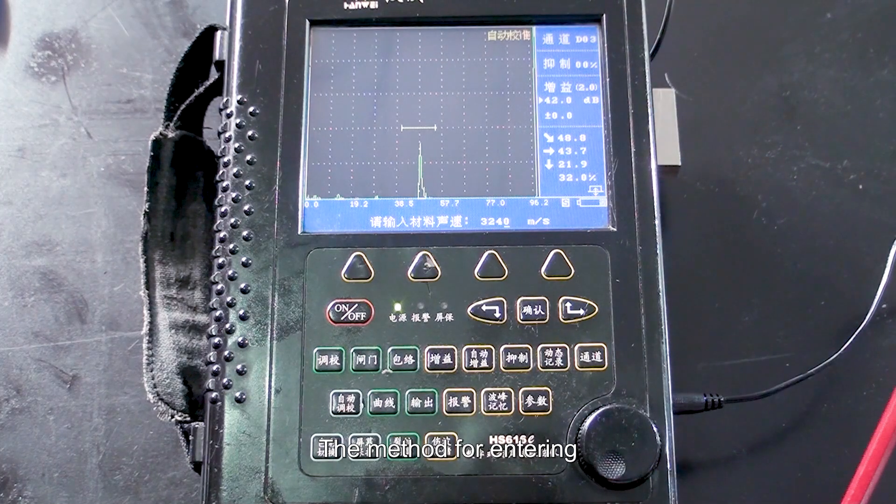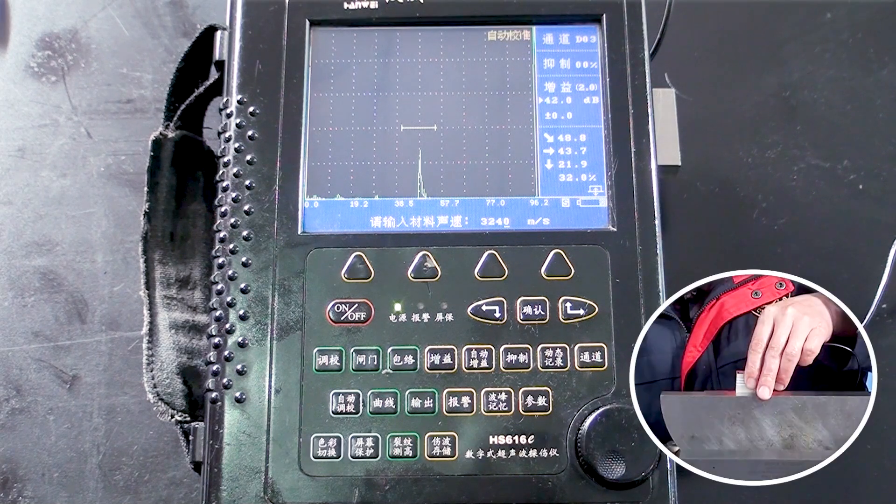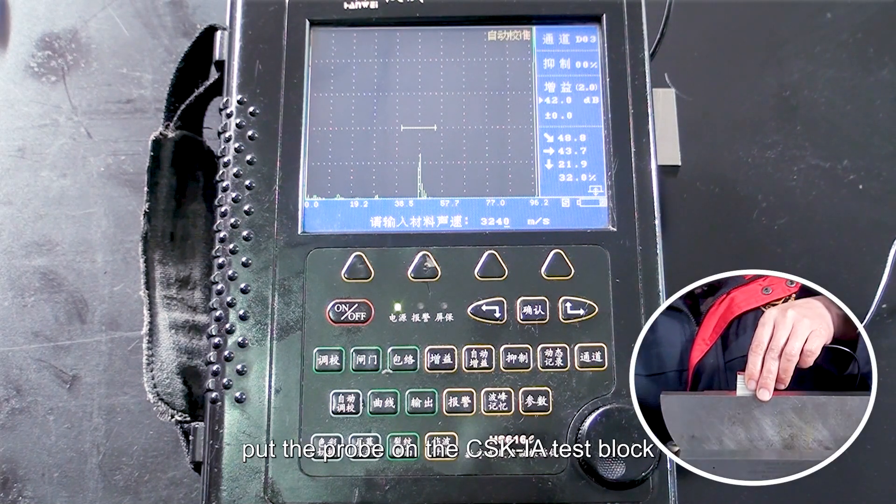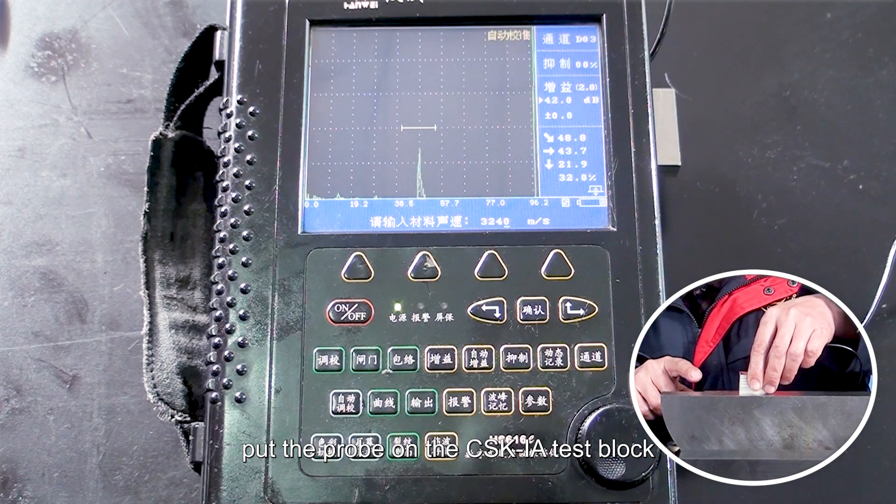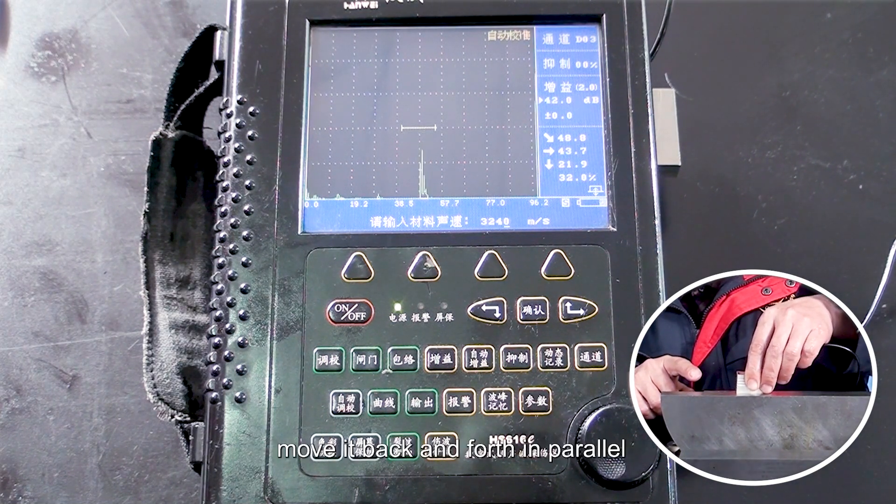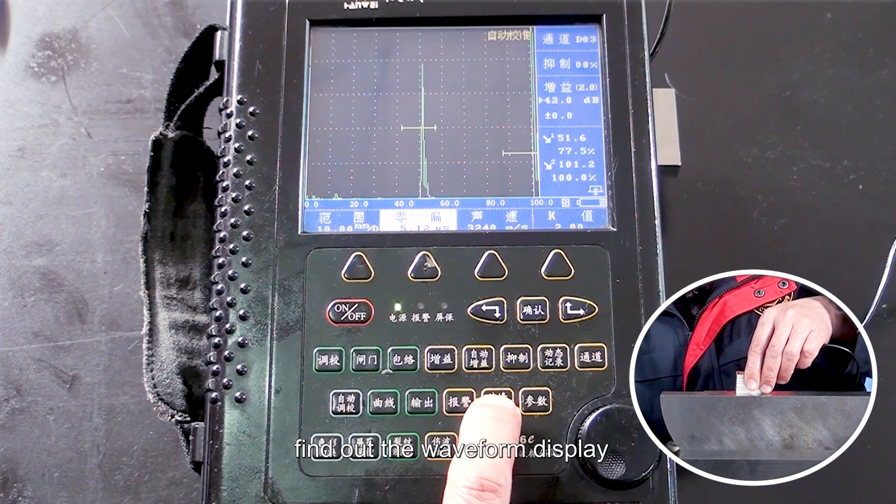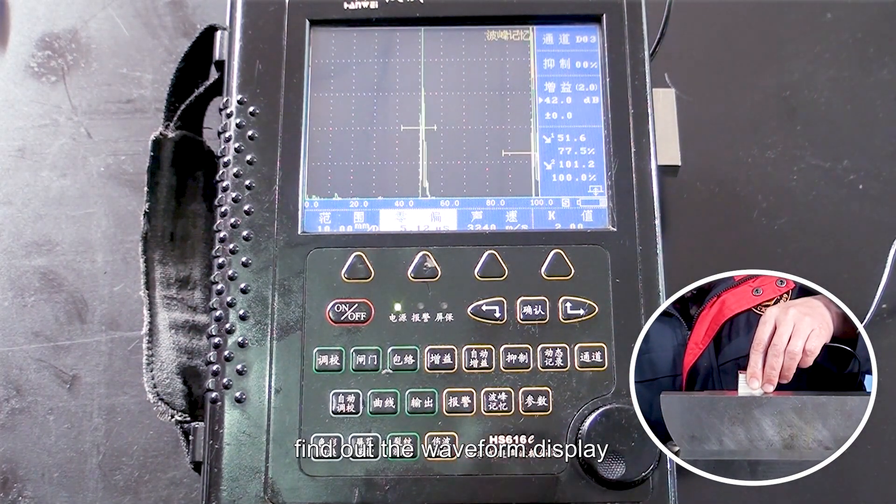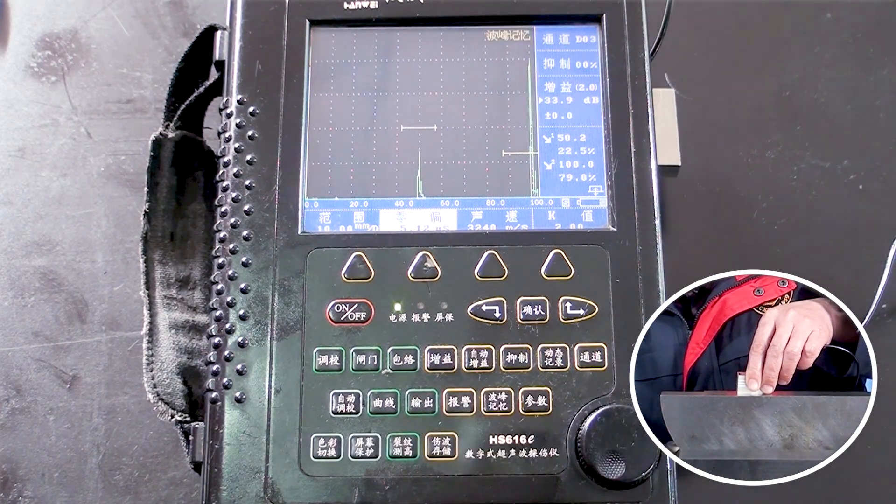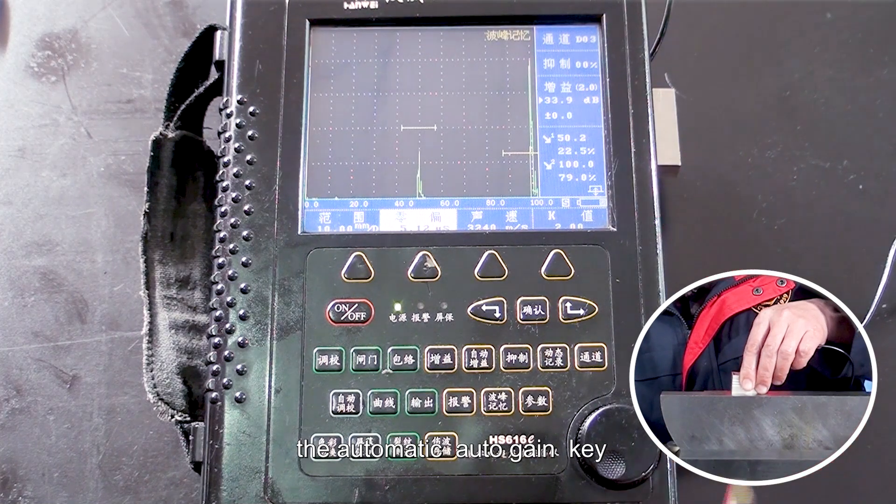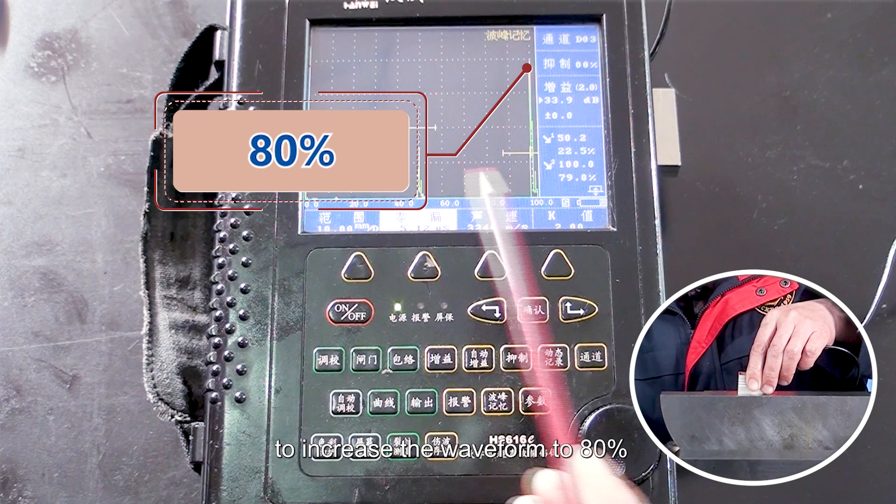The method for entering the incident point test is as follows. Put the probe on the CSK-IA test block, move it back and forth in parallel, find out the waveform display, press the peak memory key, and then press the automatic gain key to increase the waveform to 80 percent.